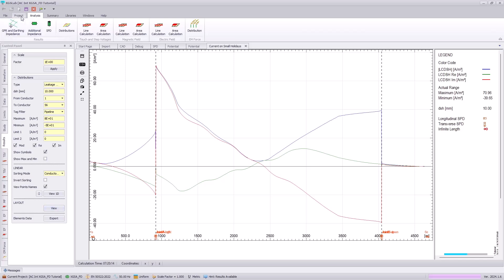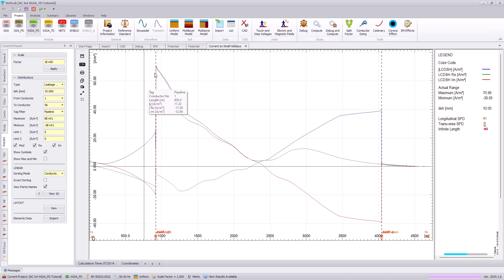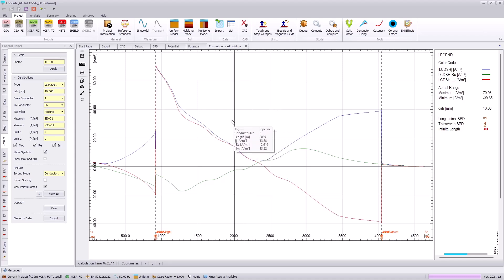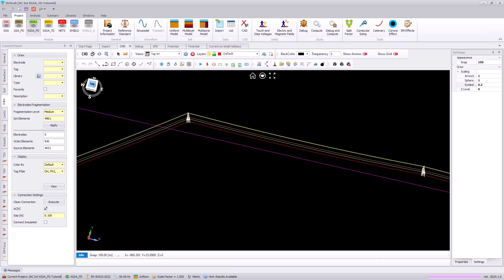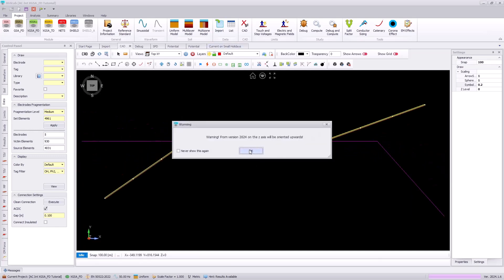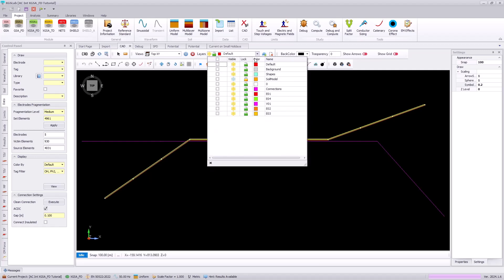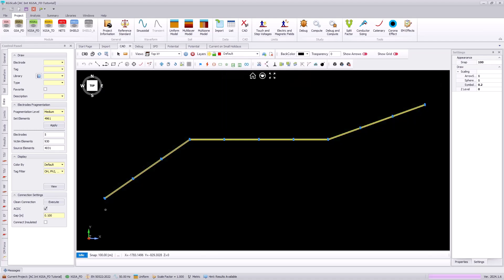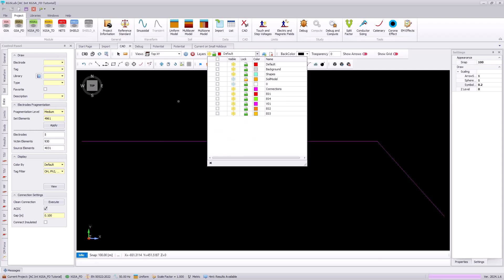The next portion of this tutorial looks into fault conditions. So far we've evaluated steady state conditions for a transmission line next to a pipeline, which evaluates pipeline voltages for personnel safety aspects as well as the current through any holiday or holes to assess AC corrosion. To facilitate the AC interference under fault conditions, we're going to import our next model. We'll first delete all of our transmission lines from the model — this speeds up the process because we do not need to re-enter our pipeline information.